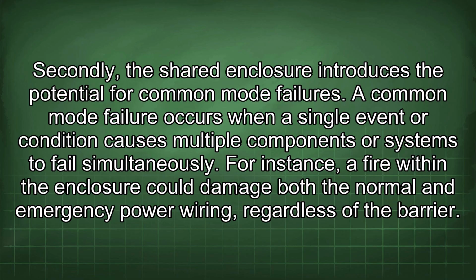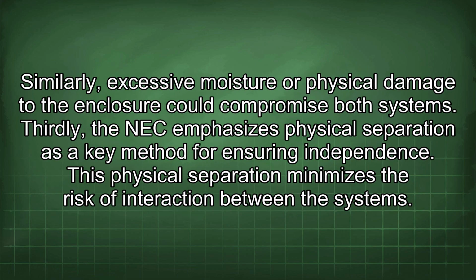A common mode failure occurs when a single event or condition causes multiple components or systems to fail simultaneously. For instance, a fire within the enclosure could damage both the normal and emergency power wiring, regardless of the barrier. Similarly, excessive moisture or physical damage to the enclosure could compromise both systems. Thirdly, the NEC emphasizes physical separation as a key method for ensuring independence. This physical separation minimizes the risk of interaction between the systems.